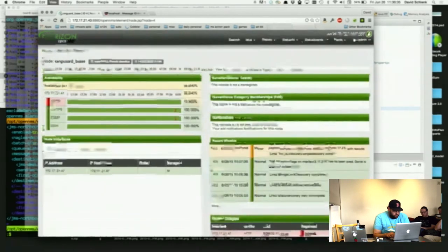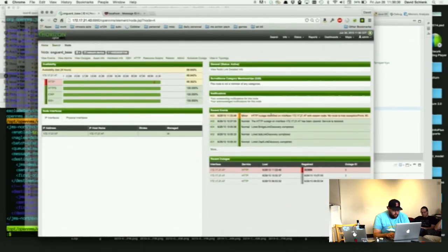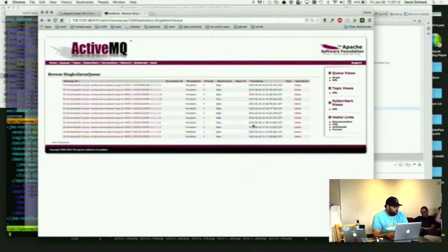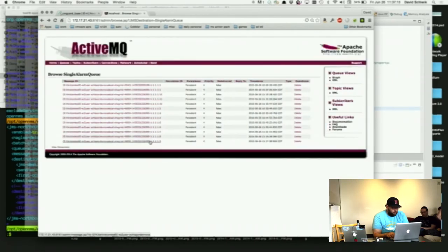So the event you're sending, is it on an alarm change? What's the relationship to the alarms themselves? Any event that has alarm data in the event definition is an alarm. Typically, alarm type 1 is a raise condition, 2 is a clear condition, and 3 is a single state, meaning that it's bad and can't fix itself. It's driven by events. Any event that has the alarm element added to it will get forwarded to this queue.